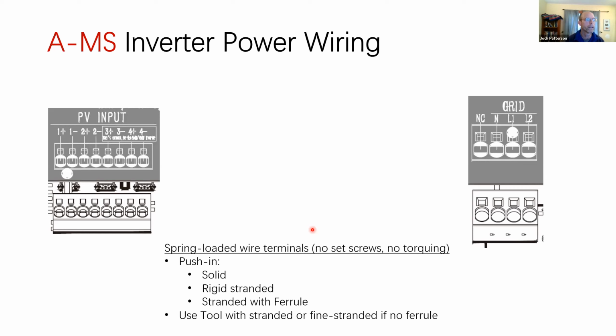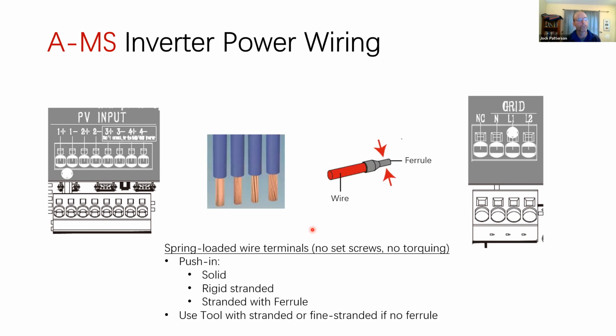On the grid side, the AC side, similar, again, screwless, spring-loaded wire terminals. So this means you can just slide the wire in if it's solid or rigid stranded. If it's fine stranded or somewhat less rigid stranded, you'll likely want to put a ferrule on it. And those ferrules exist in the inverter box, right? Our little accessory box. You'll find a bunch of ferrules. With that properly crimped, it's not only preventing the splaying of any strands as you insert it, but also means you don't need to have a tool to open up the throat of the spring-loaded terminal. You can just push it right in. It also, over time, reduces the oxidation. And so you get a better contact, less resistance over time by using ferrules.